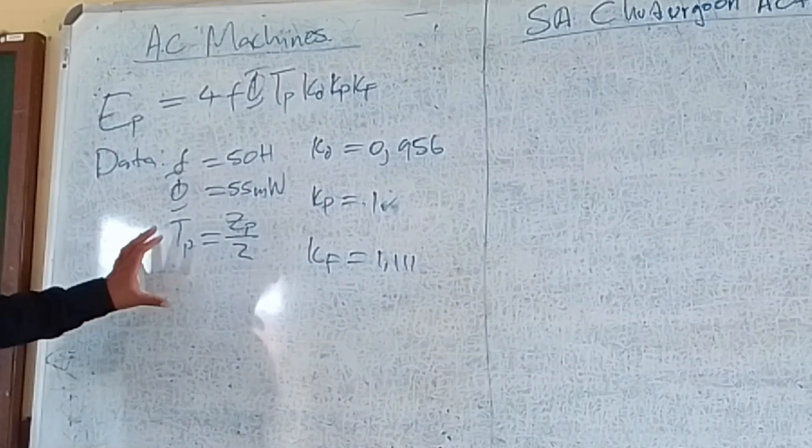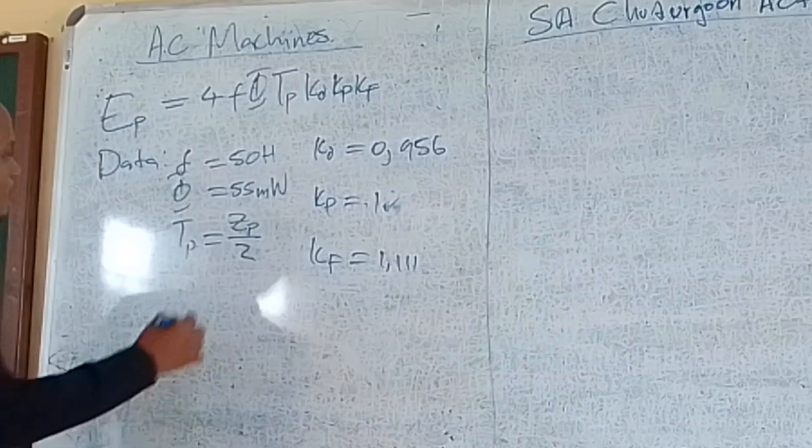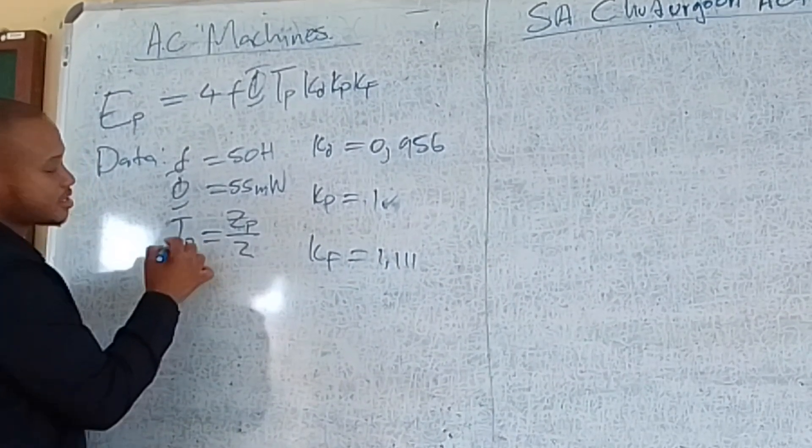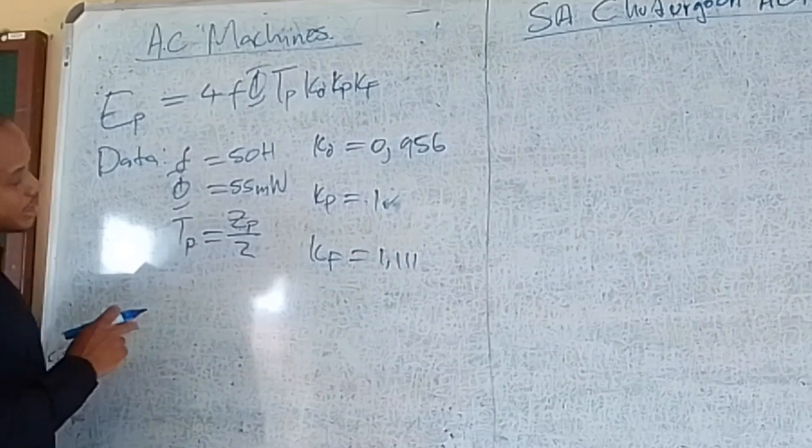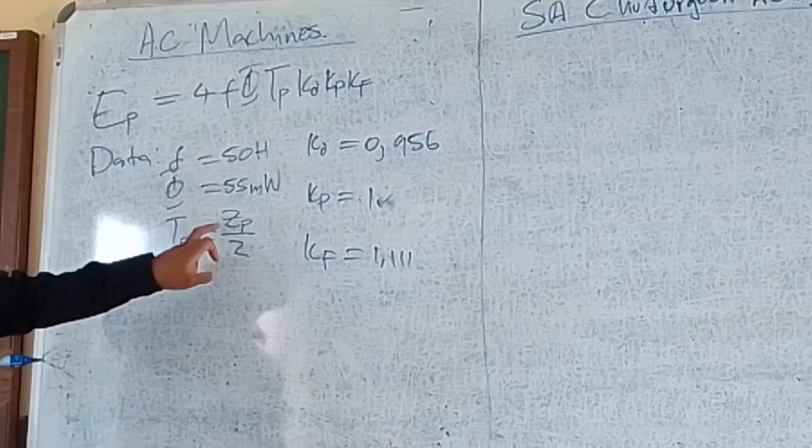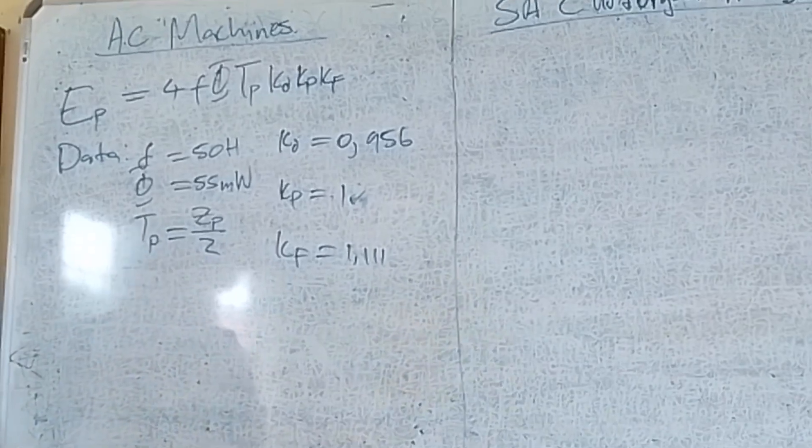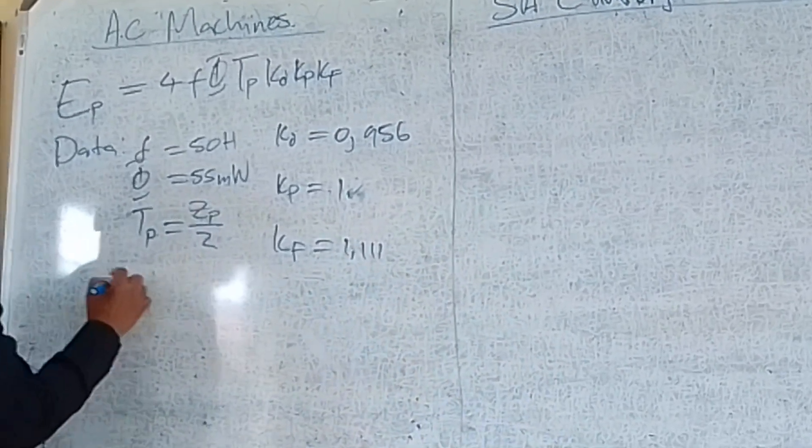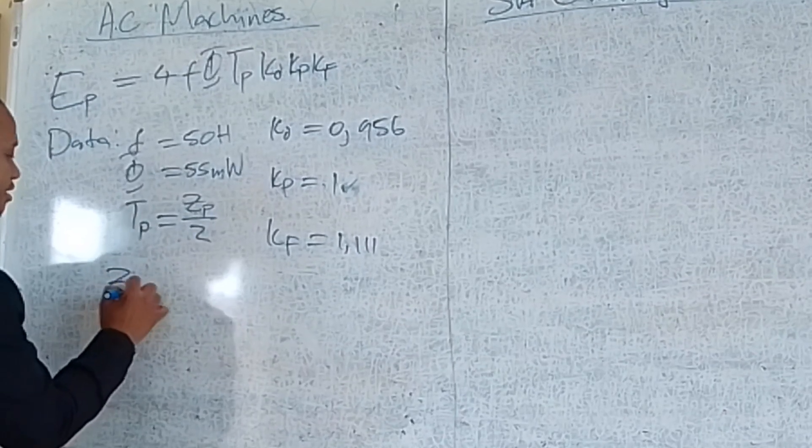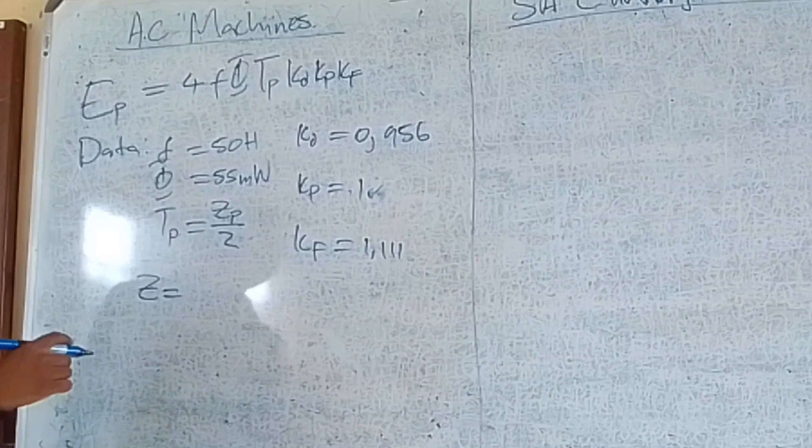We have all the other values except for one. I must calculate the turns per phase. From the equation, the turns per phase is equal to the total number of conductors in the phase divided by 2. I must calculate Z, which is the number of conductors in the machine.